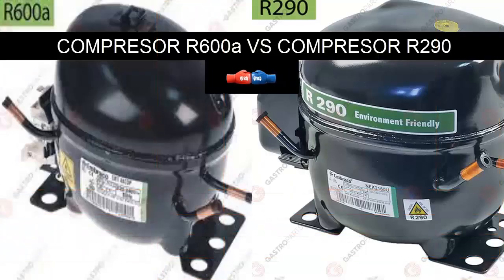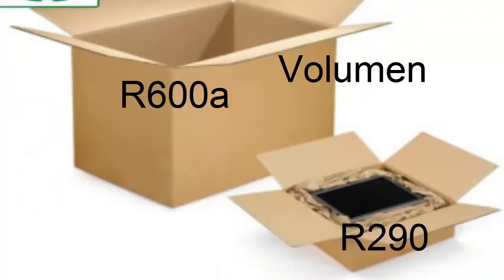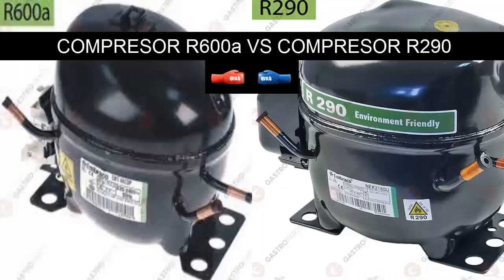Thus, to equalize, the R600a compressor requires an increase in displacement. This is why the R600a compressor tends to be larger in terms of volume compared to an R290 compressor with the same cooling capacity. Regarding oil compatibility, both R600a and R290 are compatible with mineral oil, alkylbenzene, and polyester oil, POE.